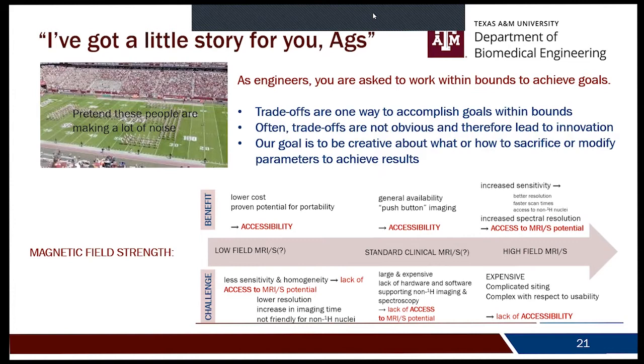At clinical field strengths — 1.5 T and 3 T — you can't push these around on a cart, but usability is better because a tech just pushes a button for the scan type, not entering every parameter manually. At high field, you gain access to immense information in the human body that you can't see at lower field strengths, but it's expensive, complicated, and extremely complex with respect to usability.